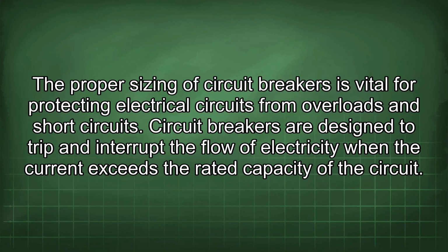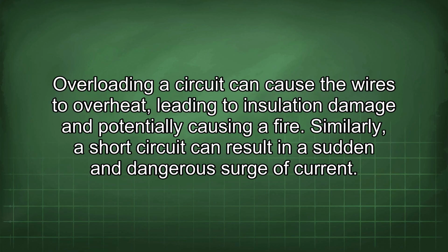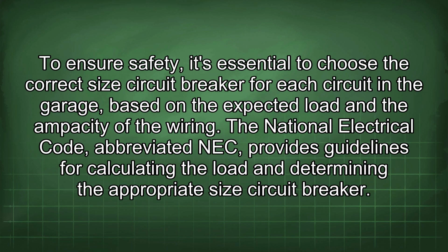The proper sizing of circuit breakers is vital for protecting electrical circuits from overloads and short circuits. Circuit breakers are designed to trip and interrupt the flow of electricity when the current exceeds the rated capacity of the circuit. Overloading a circuit can cause the wires to overheat, leading to insulation damage and potentially causing a fire. Similarly, a short circuit can result in a sudden and dangerous surge of current. To ensure safety, it's essential to choose the correct size circuit breaker for each circuit in the garage, based on the expected load and the ampacity of the wiring.